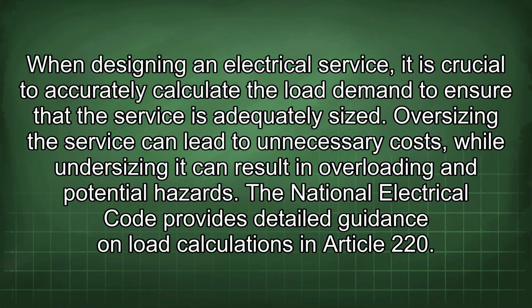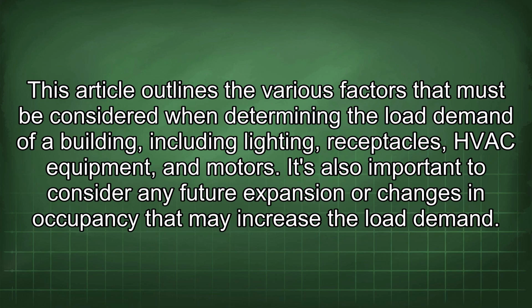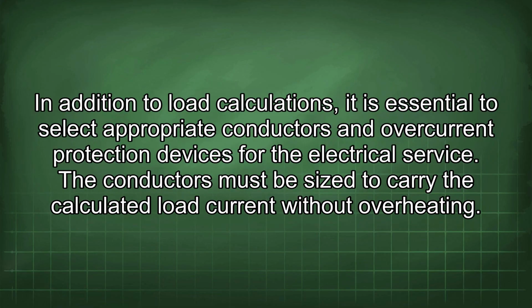The National Electrical Code provides detailed guidance on load calculations in Article 220. This article outlines the various factors that must be considered when determining the load demand of a building, including lighting, receptacles, HVAC equipment, and motors. It's also important to consider any future expansion or changes in occupancy that may increase the load demand. In addition to load calculations, it is essential to select appropriate conductors and overcurrent protection devices for the electrical service.